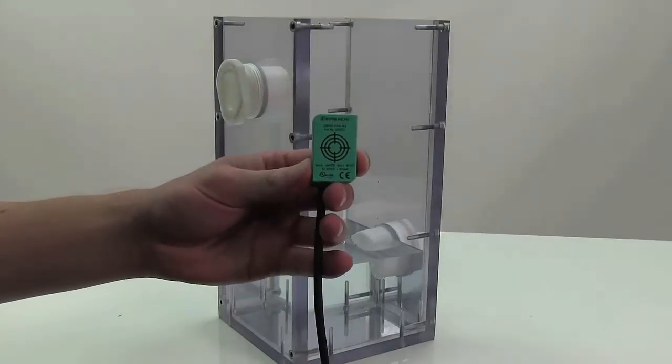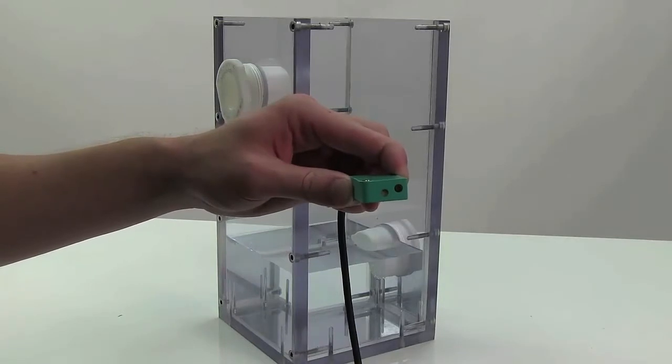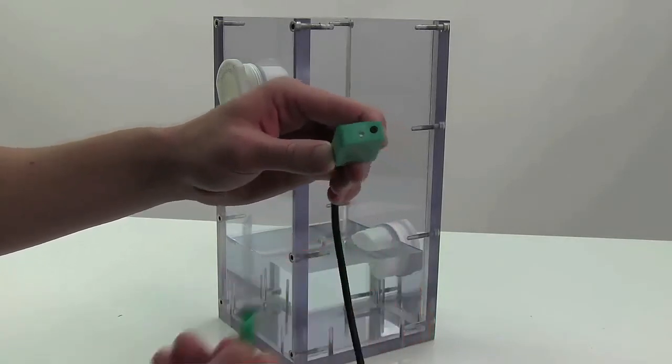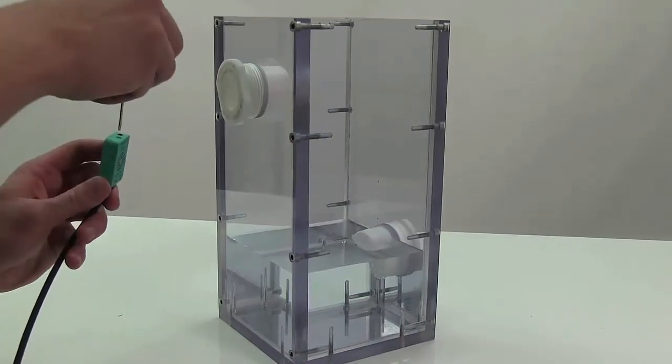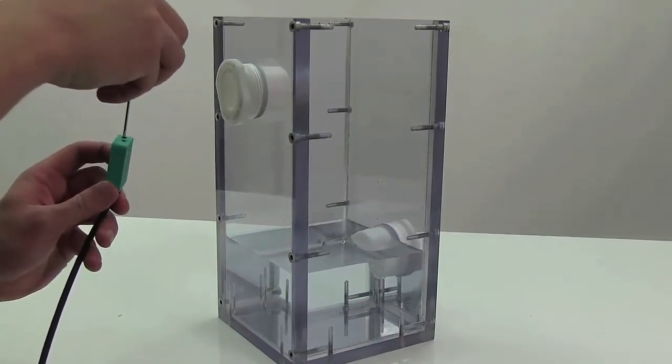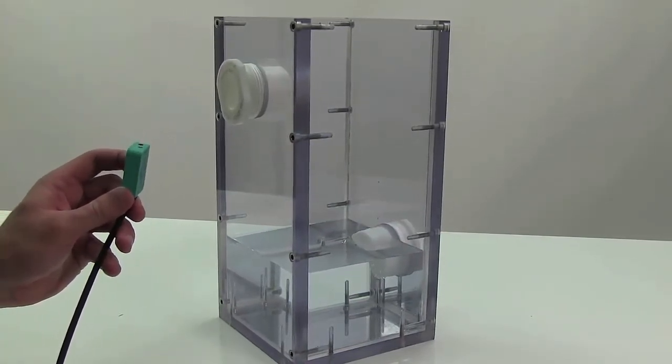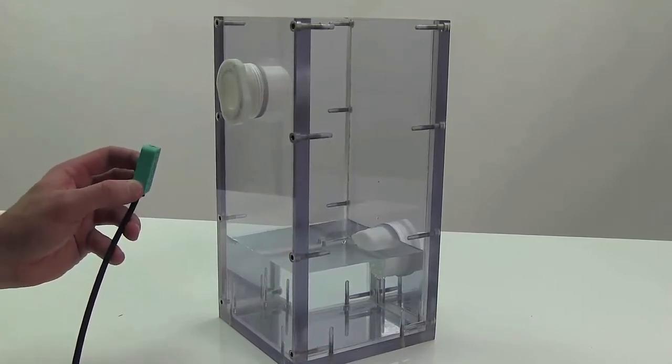This CBN15 has a potentiometer on the top that can be adjusted by a small flat head screwdriver. To start your sensor calibration, rotate the potentiometer counterclockwise until you hear a click. This will indicate that the sensor is on its lowest sensitivity setting.